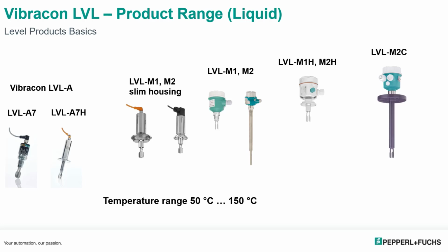The next versions are the LVL M1s and M2s. The M1 is a standard length, and the M2 you can get with an extended length probe. And the LVL M1H and M2H, again, the H indicates the hygienic type, tri-clamp fittings and so on. And then the LVL-M2C, which is a coated probe for very corrosive areas where Hastelloy or even stainless steel are corroded.